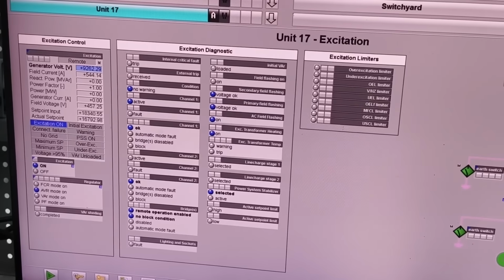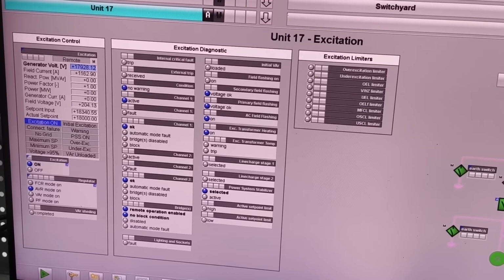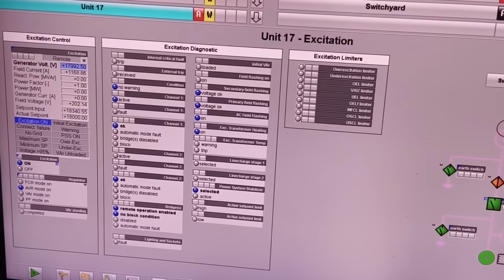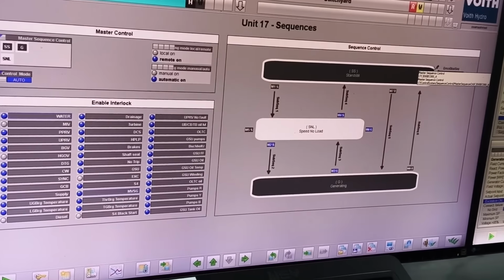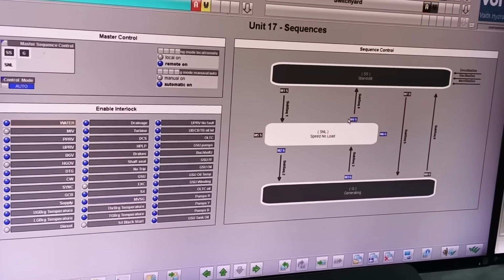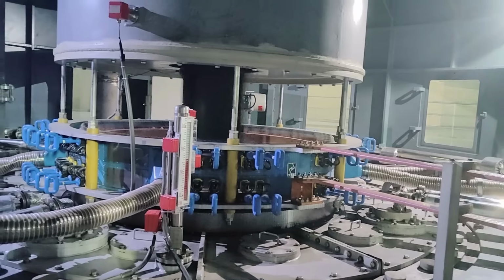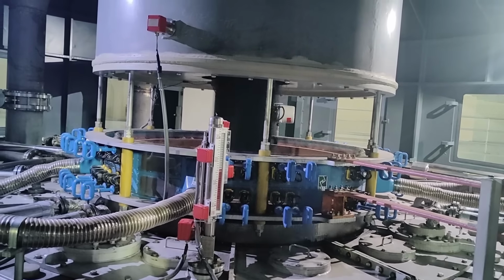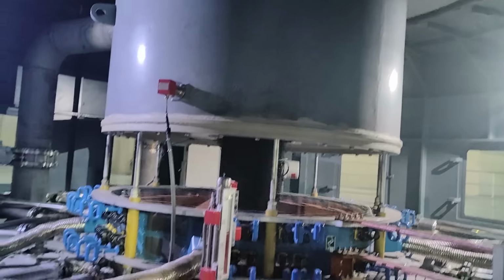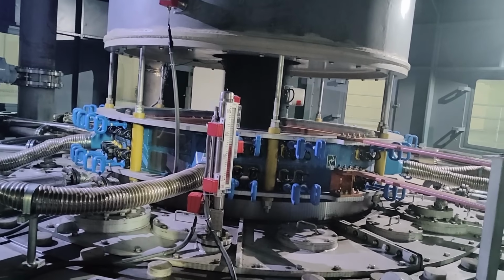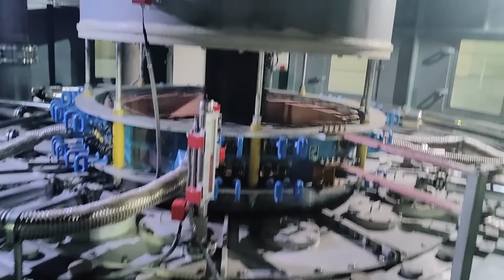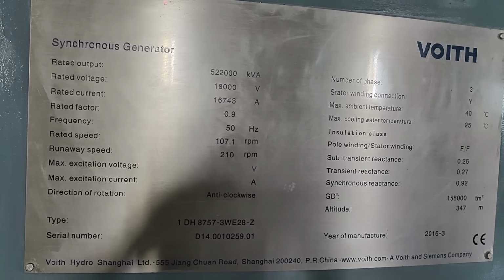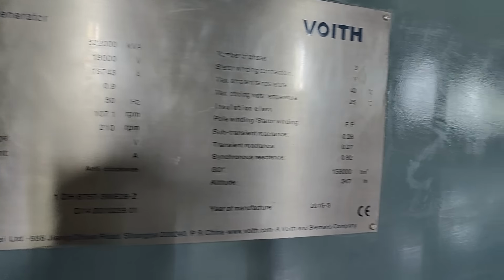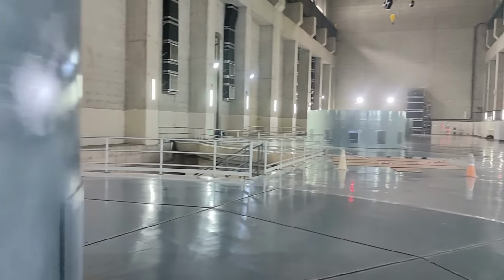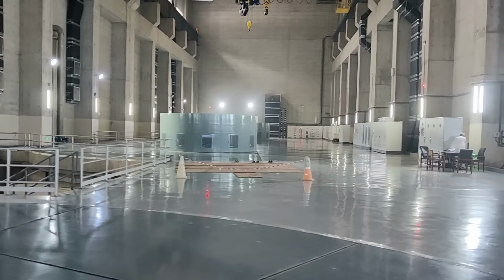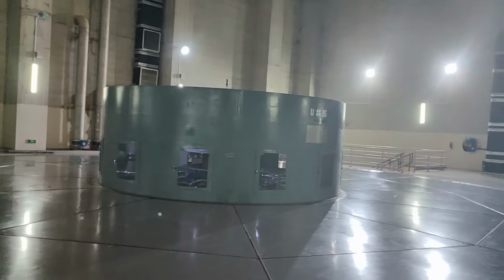Okay, now the turbine is near rated speed, but the generator still cannot produce electricity because rotation alone is not enough, and the generator now needs excitation. So the excitation system supplies direct current into the rotor winding, creating a powerful rotating magnetic field, and this is where the invisible physics finally becomes electrical power. As the magnetic field rotates inside the rotor, electromagnetic induction begins generating voltage at the generator terminals. The voltage gradually rises towards rated value.